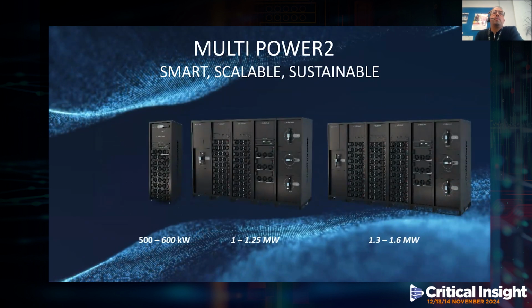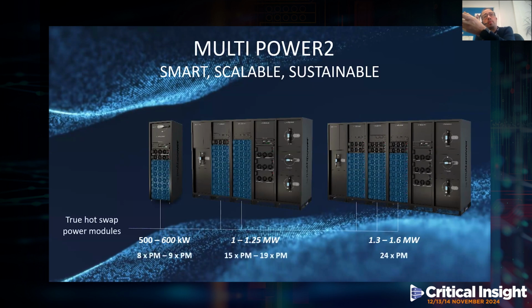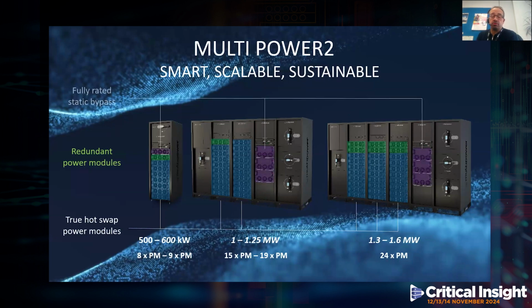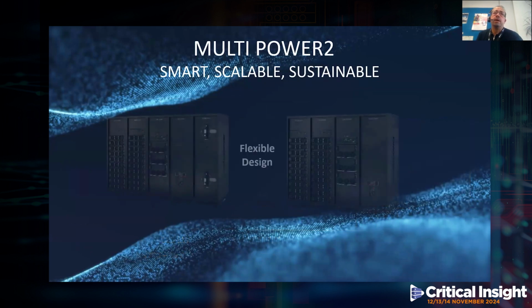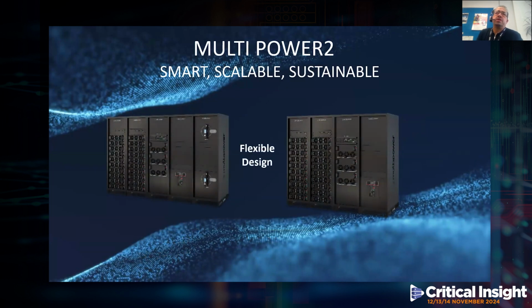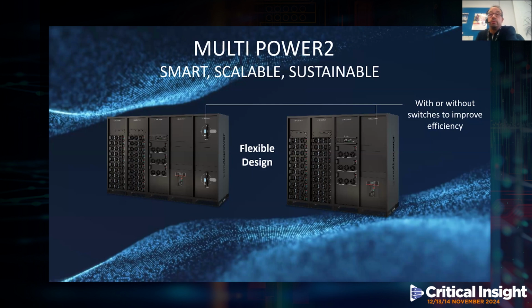Now, like all modular solutions, the cabinets are populated with power modules. However, unlike some other systems, these modules are all truly hot swappable, and the cabinets have spare capacity for redundant modules. And all cabinets come as standard with a fully rated centralized static bypass system. Now, the Multi-Power 2 has been specifically designed with flexibility in mind, making it compatible with most infrastructure environments. The cabinets themselves can be supplied with or without power switches, which can help improve the overall system efficiency by approximately 0.1%. Let's face it, every little helps.